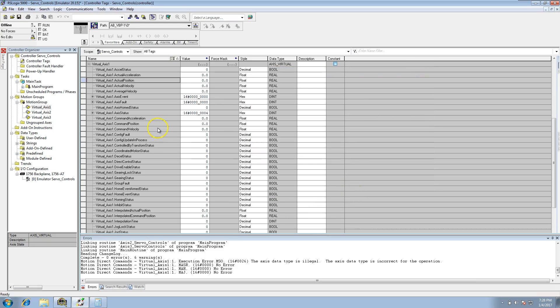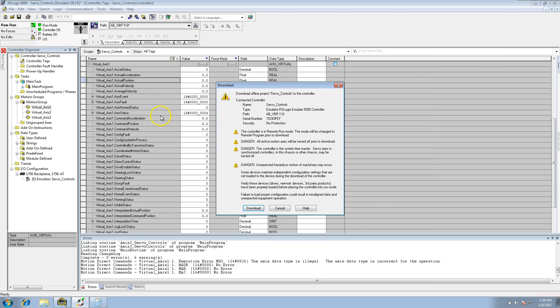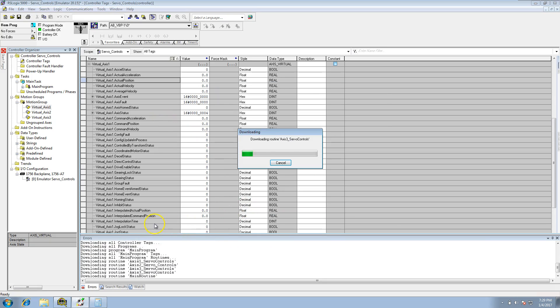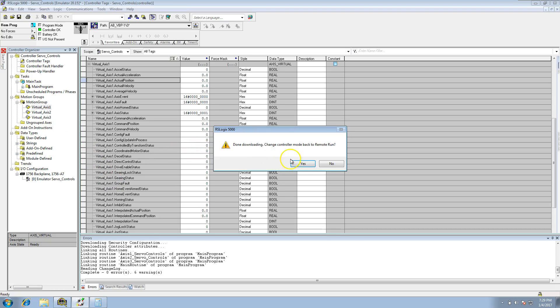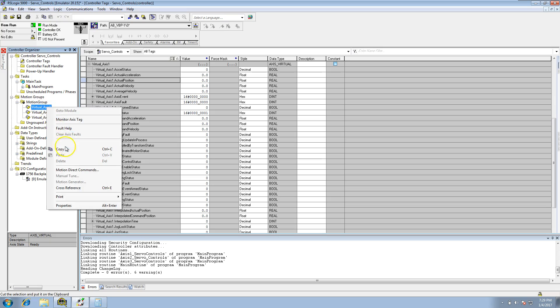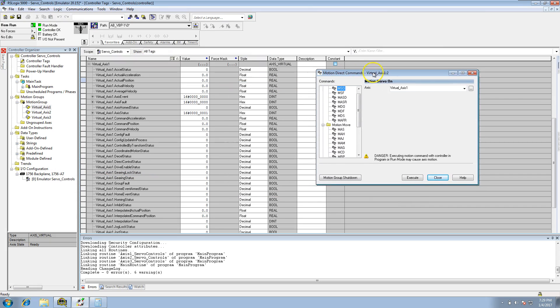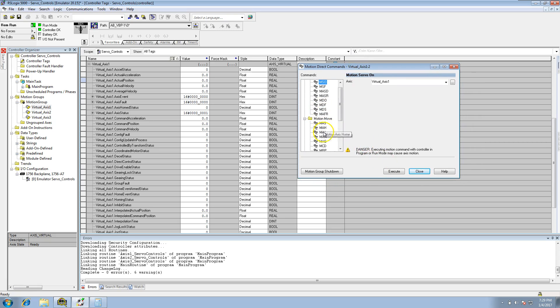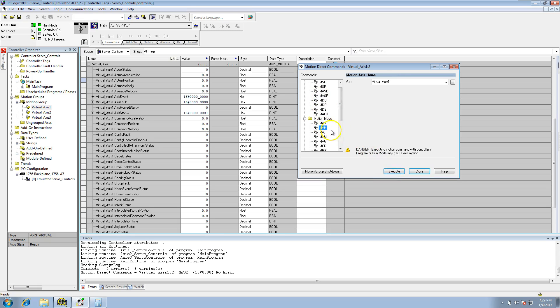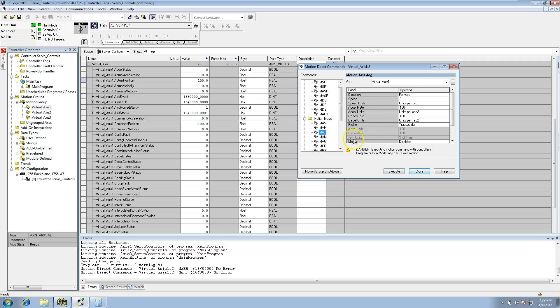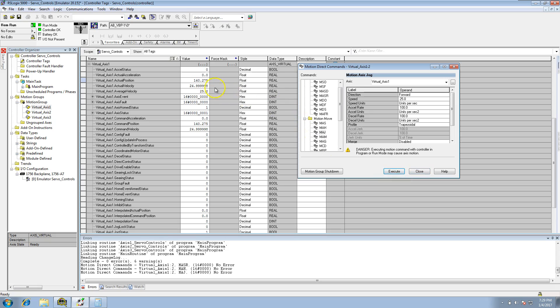We save that and download. We go to motion axis direct commands to see how it works. We clear the faults, home it, then jog it again. This will start jogging and run up to 360 degrees on the actual position, then change over to zero. This number in the actual position — when it hits 360 degrees, it will flip over to zero, just like that.